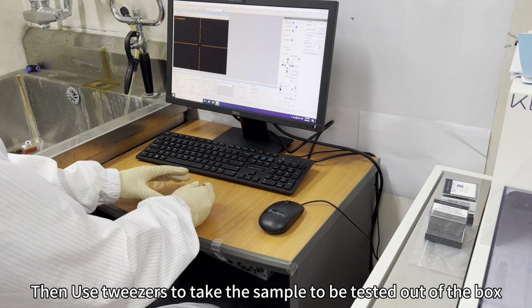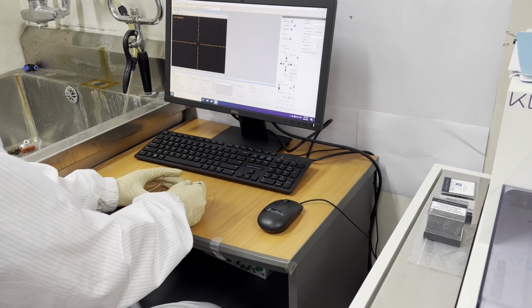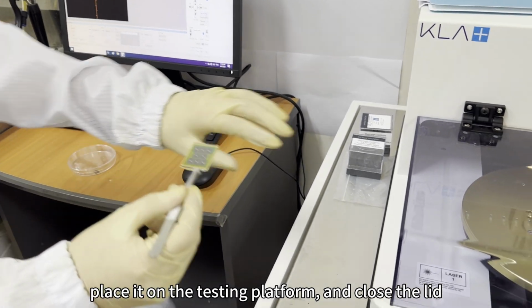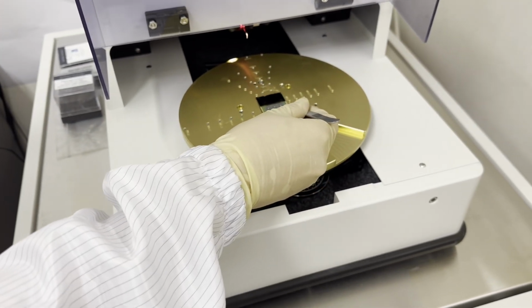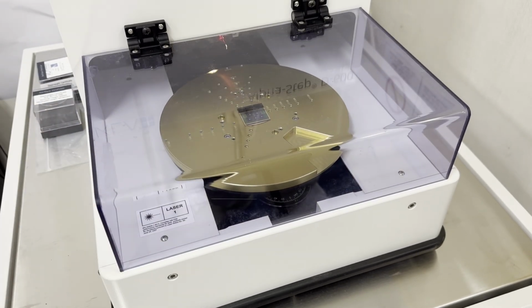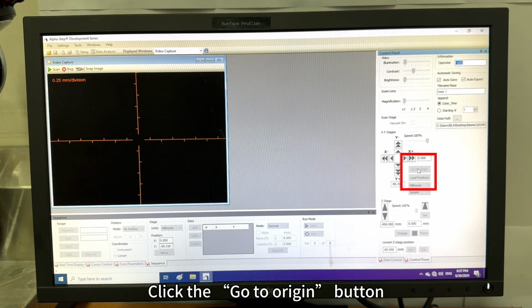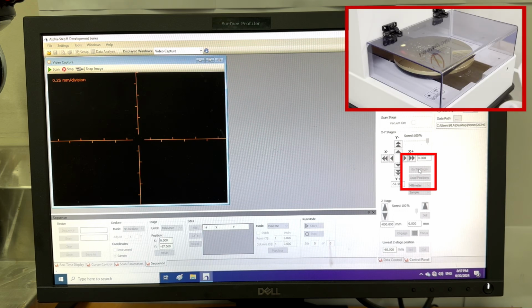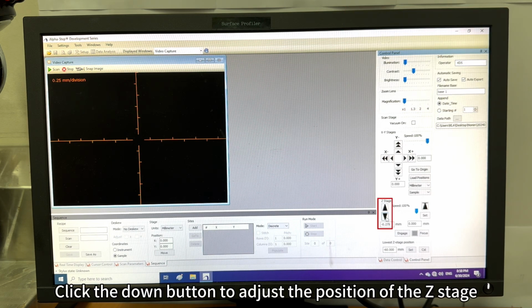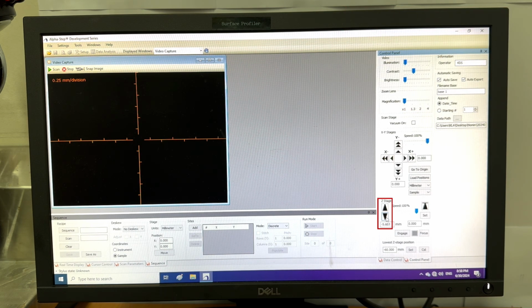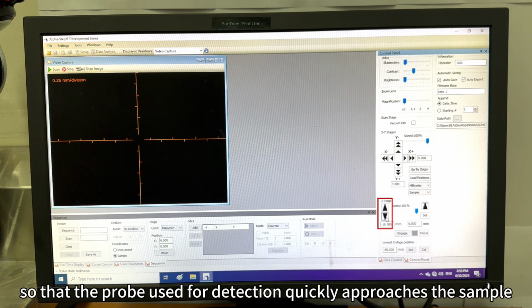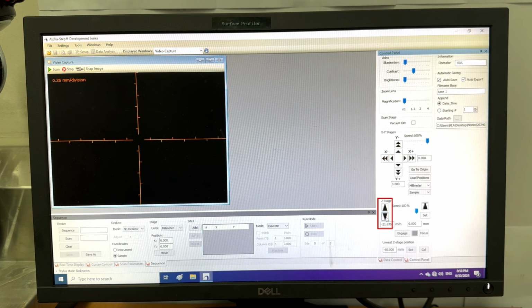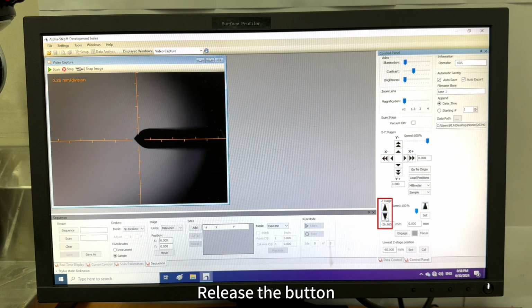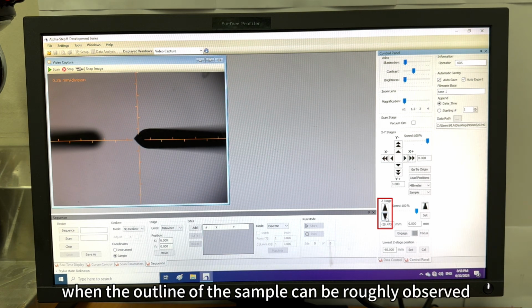Then use tweezers to take the sample to be tested out of the box. Place it on the testing platform and close the lid. Click the Go to Origin button to move the sample to the detection area. Click the down button to adjust the position of the Z stage, so that the probe used for detection quickly approaches the sample. Release the button when the outline of the sample can be roughly observed.